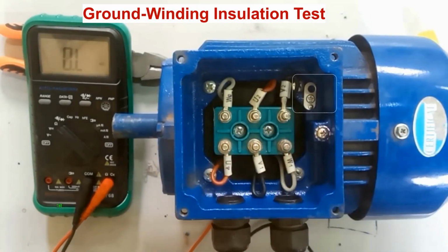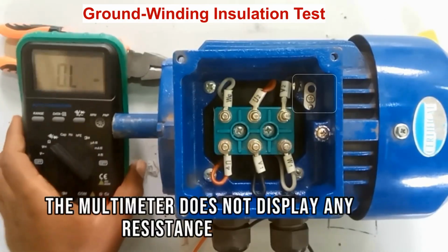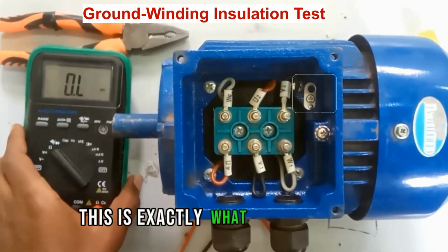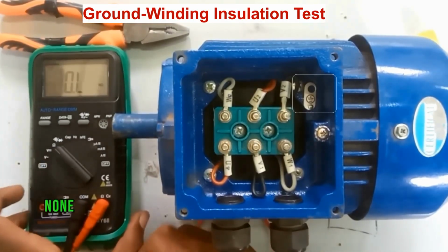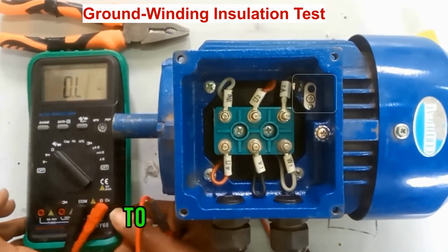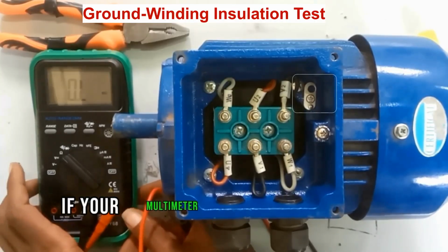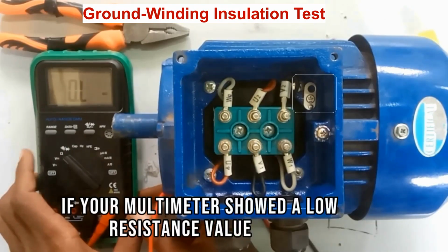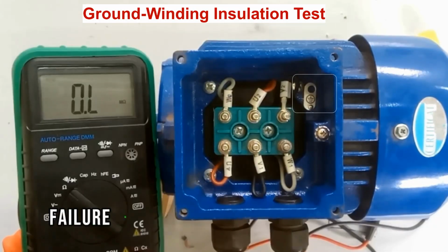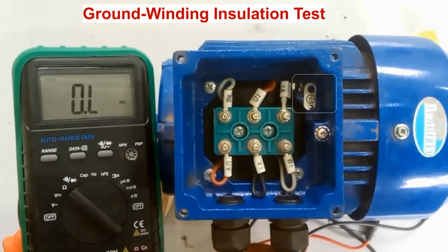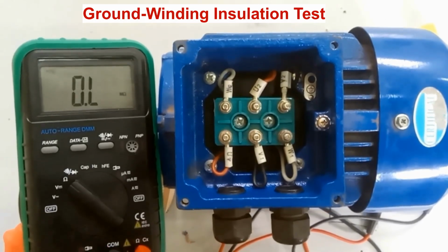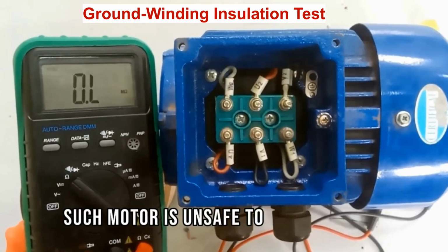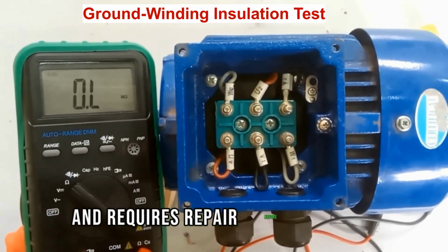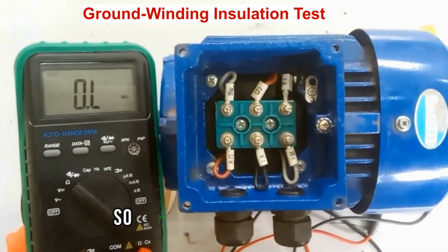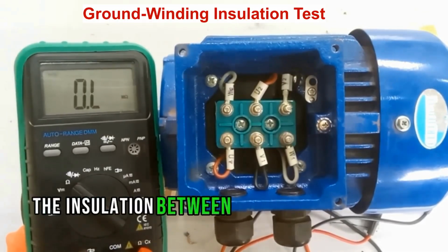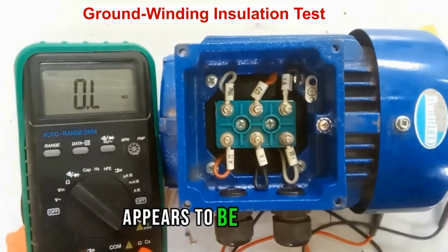As you can see, the multimeter does not display any resistance reading. This is exactly what we want. That means none of the windings are electrically connected to the motor body. If your multimeter showed a low resistance value here, it would indicate insulation failure or a short circuit to ground. Such a motor is unsafe to energize and requires repair before use. So, based on this test, the insulation between the winding and the motor frame appears to be good.